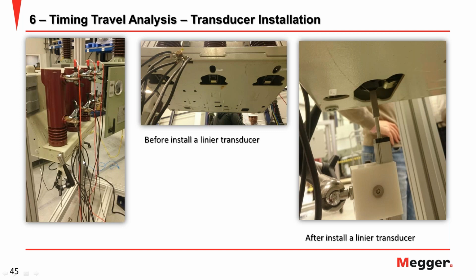This is the example of the MV breaker, but I know this is in the training session. We can put the linear. If you see the bottom part of the breaker, this is the mechanical part. Sorry, the breaker here position when breaker open and close. There is a link that can move up and down. You can see here this link will be moved up and down. From this part, you can connect our linear transducer. So if you see the breaker open and close, this transducer will move the same as the breaker up and down. This is how to install the linear transducer if you can connect to the breaker.